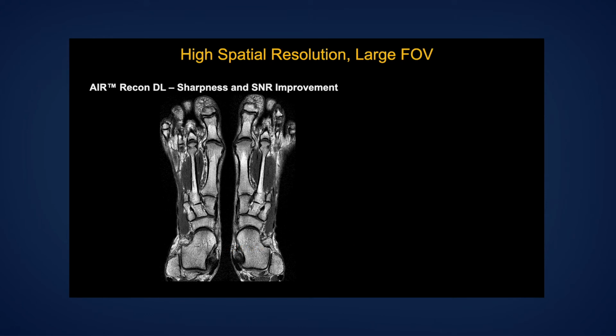Another similar theme, but slightly different, is the use of AIR Recon DL to obtain very large fields of view, which typically would result in penalties related to spatial resolution. If you obtain a very large field of view, you'd have to go really, really high on your matrix size in order to maintain your in-plane resolution, and this incurs a time penalty.